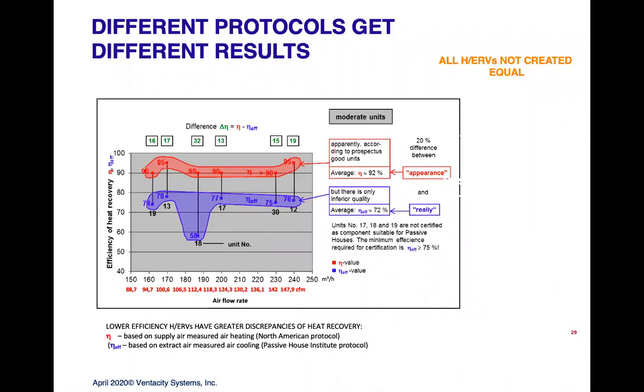So when you measure that efficiency, it has quite a few potential issues in there: the waste heat from the motors, the cross-flow contamination I talked about, and what they call casing leakage, where, if that unit is inside the building, it could be warming up the air just by going through an uninsulated side of their HRV or ERV.